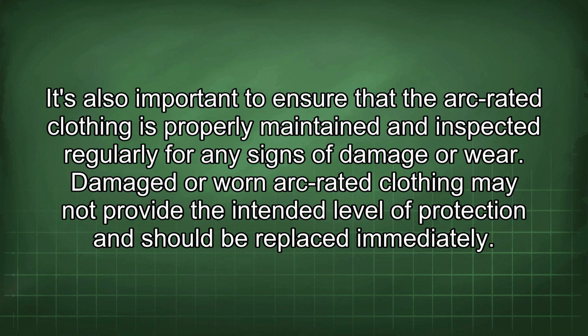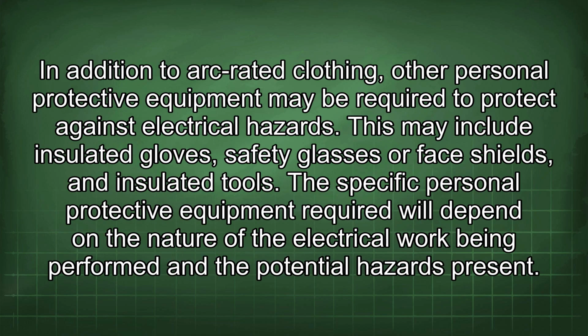It's also important to ensure that the arc-rated clothing is properly maintained and inspected regularly for any signs of damage or wear. Damaged or worn arc-rated clothing may not provide the intended level of protection and should be replaced immediately. In addition to arc-rated clothing, other personal protective equipment may be required to protect against electrical hazards. This may include insulated gloves, safety glasses or face shields, and insulated tools. The specific personal protective equipment required will depend on the nature of the electrical work being performed and the potential hazards present.